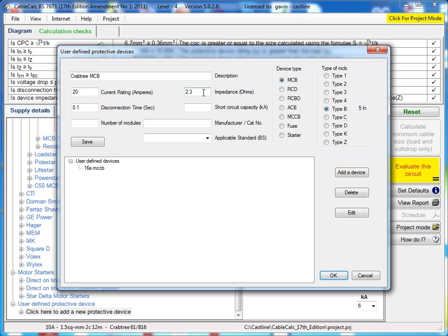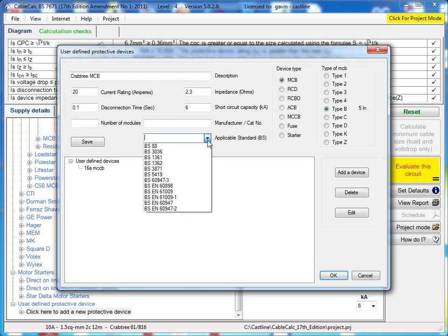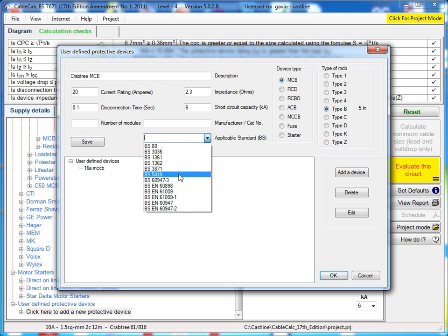It'll tell you the maximum permitted impedance calculated straight away. You can alter that if you're required. Also, you can enter the short circuit capacity, how many modules it takes up in the board, as well as the catalogue number, and then what BS it applies to the device.